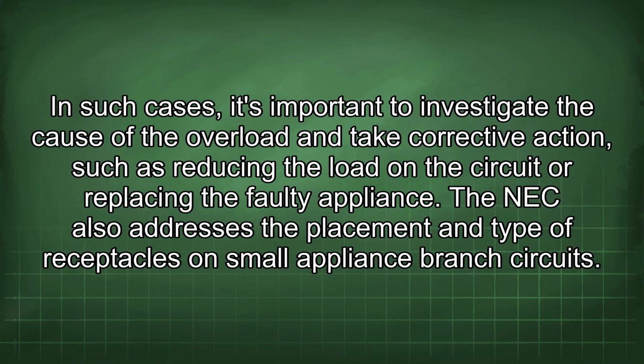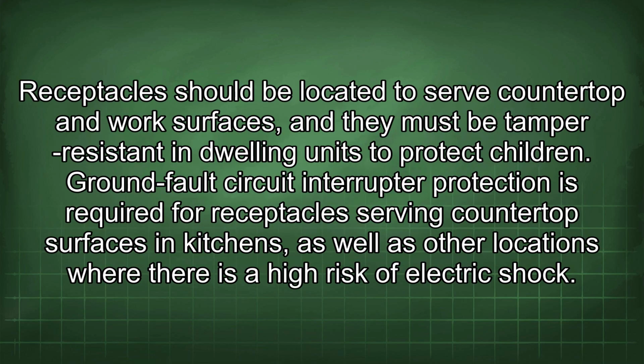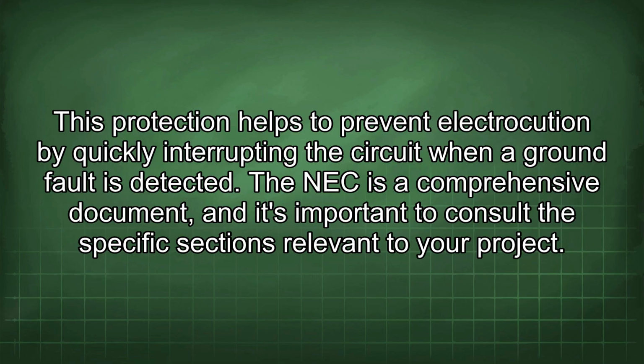The NEC also addresses the placement and type of receptacles on small appliance branch circuits. Receptacles should be located to serve countertop and work surfaces, and they must be tamper-resistant in dwelling units to protect children. Ground fault circuit interrupter protection is required for receptacles serving countertop surfaces in kitchens, as well as other locations where there is a high risk of electric shock. This protection helps to prevent electrocution by quickly interrupting the circuit when a ground fault is detected.